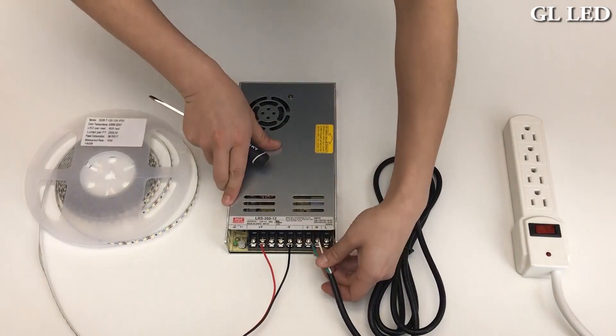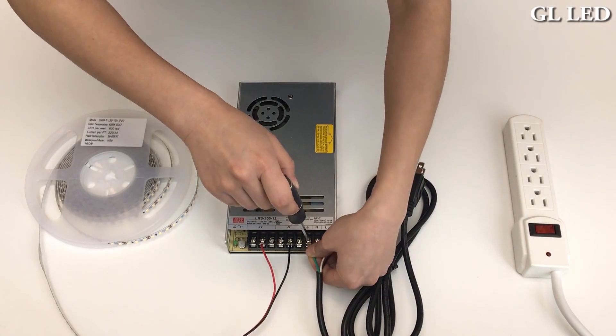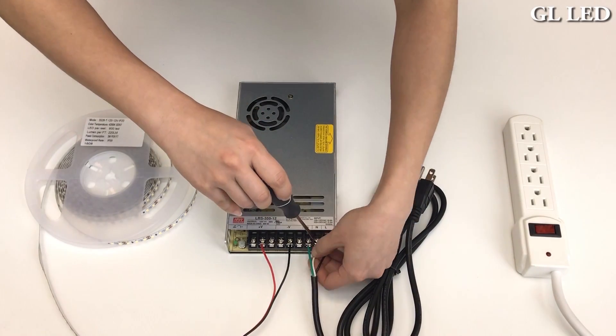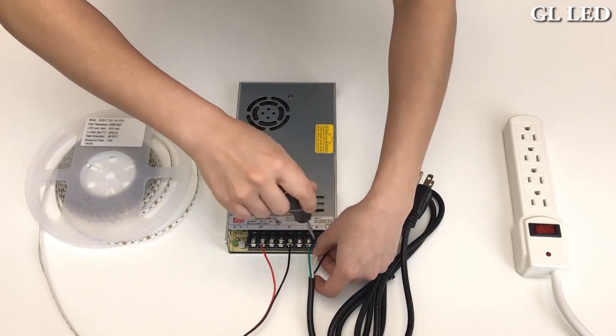Next, connect in your input section your AC cord. Your green wire is your ground wire. The white wire is your neutral wire. Then lastly, the black wire is your line wire.